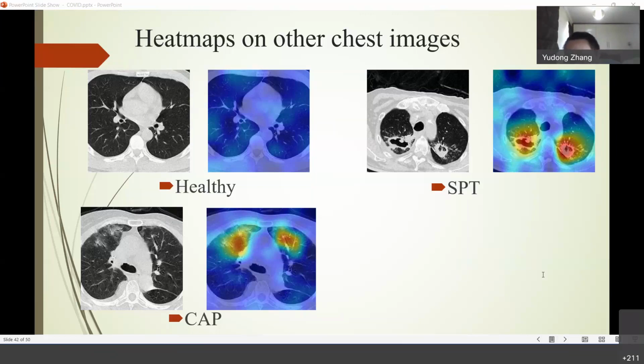Okay. So what about the validation for the results, since this model is going to use deep learning? Yes, it's true. Even if you get very excellent results via computer simulation, we still need to go through some strict medical validation before we can apply it to the medical environment. So what we can do is use some remote servers, like the video I shared with you. We requested the doctors to get access to our UI, our web app, and they can give some feedback.